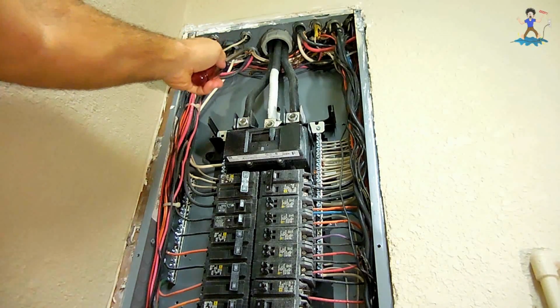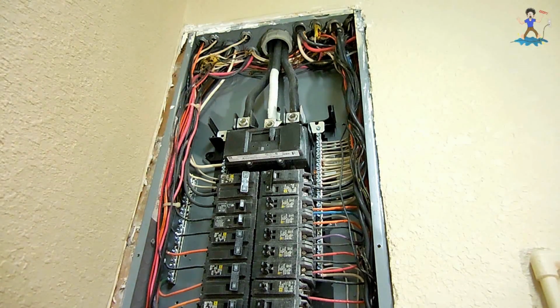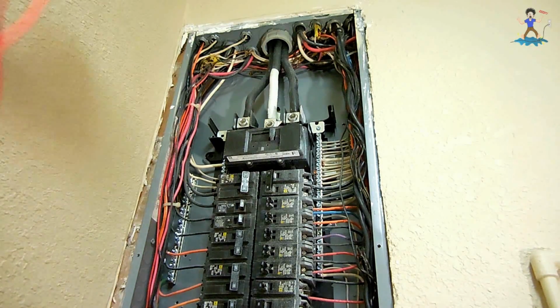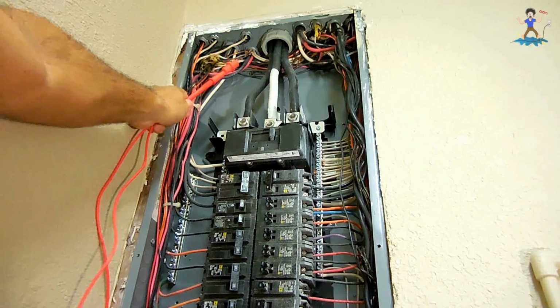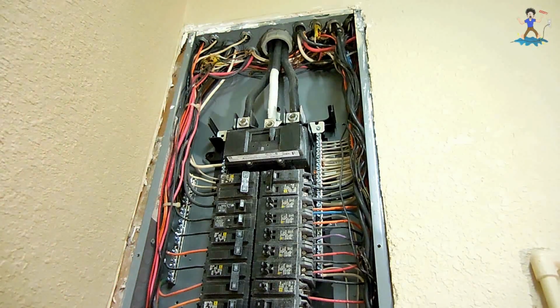If I pull through a red 12 gauge wire, once that wire is pulled through that conduit with the other wires, you're going to want to check that wire to make sure it's well isolated from the ground as well as the other wires in the conduit. So you're going to repeat the procedure. The black lead on the ground bar inside the panel or the enclosure. You're going to take the red lead and connect it to the red wire you just pulled into the panel, and you could set the Megger to 250 volts and perform the test. The reading you get should be a high reading.